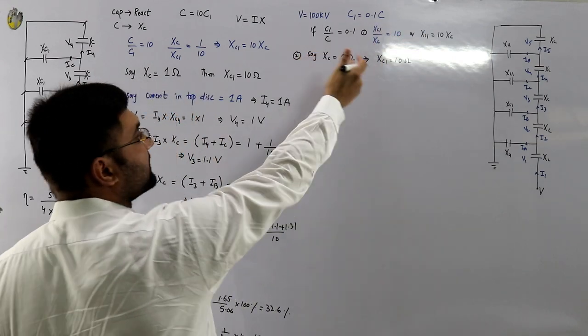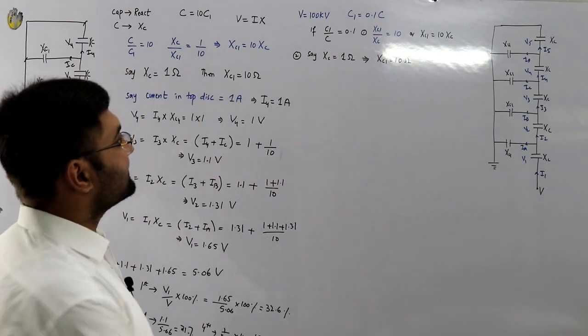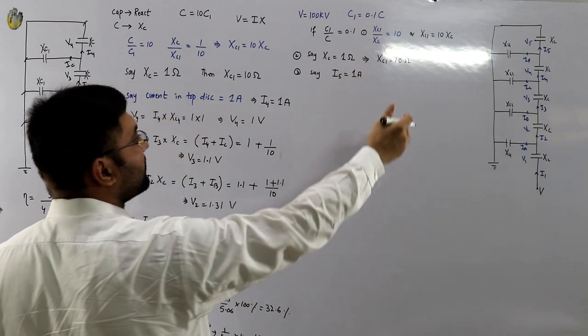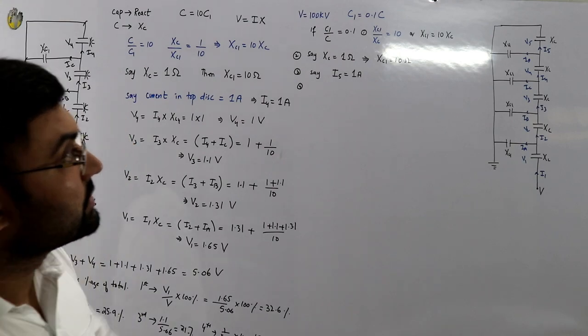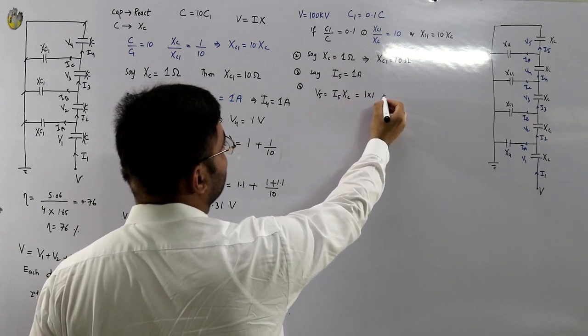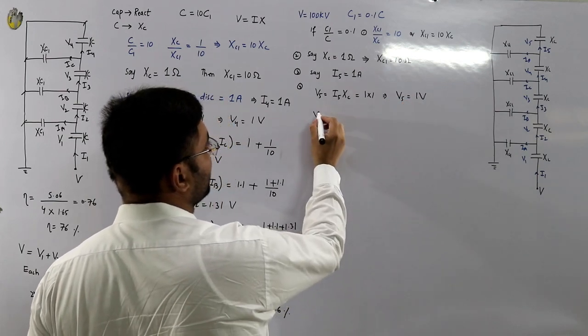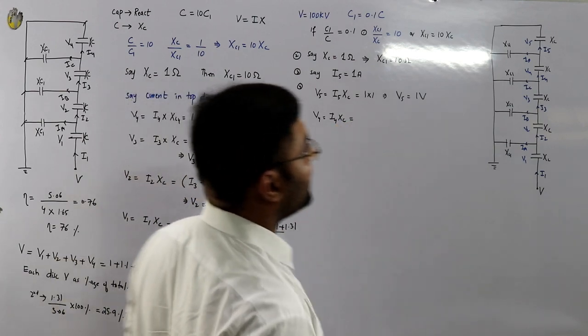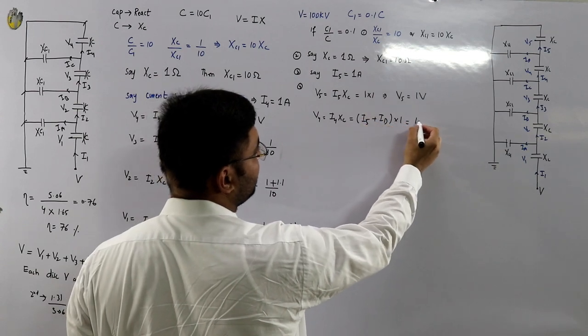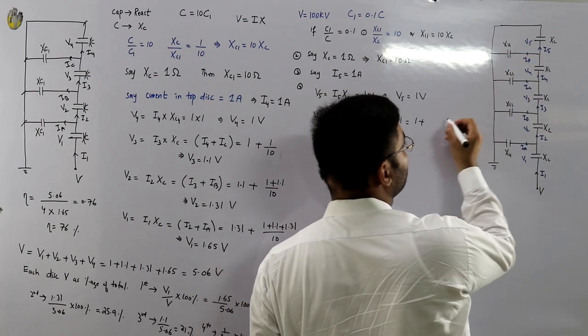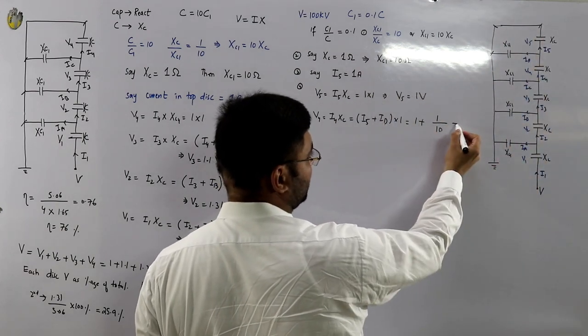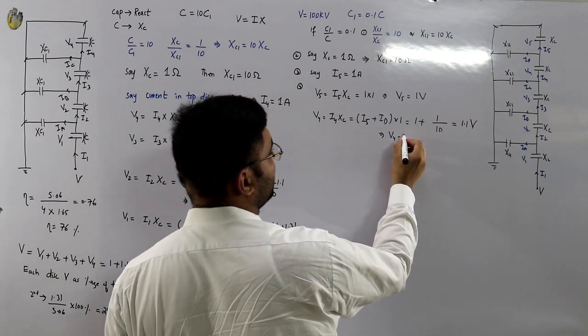The method steps are: Step 1 — replace capacitances by reactances. Step 2 — assign Xc = 1 ohm, so Xc1 = 10 ohms. Step 3 — assume current in the top disc I5 = 1 ampere. Step 4 — find voltage distributions. V5 equals I5 × Xc = 1 × 1 = 1 volt. V4 equals I4 × Xc, where I4 = I5 + Id = 1 + (V5/Xc1) = 1 + 0.1 = 1.1, so V4 = 1.1 volts.